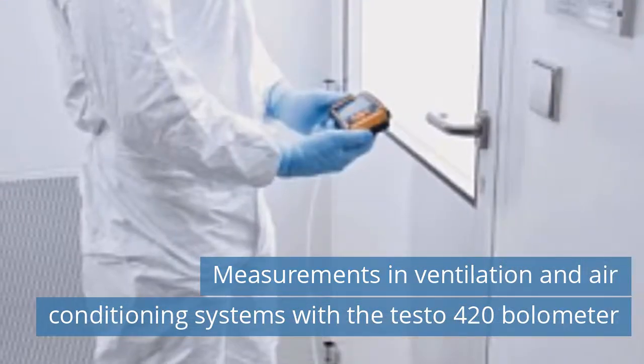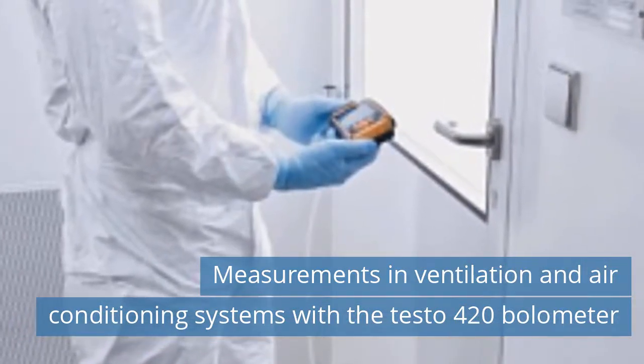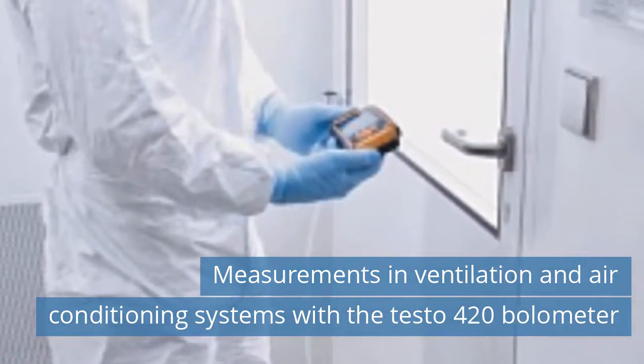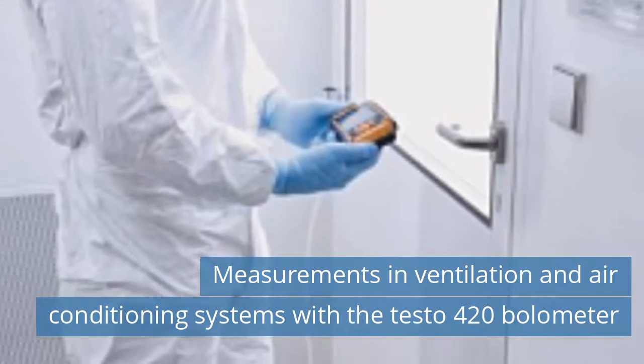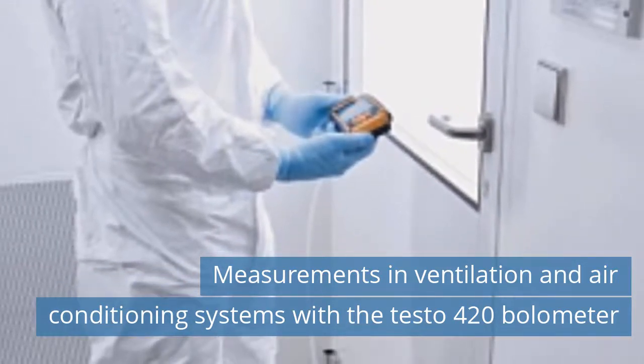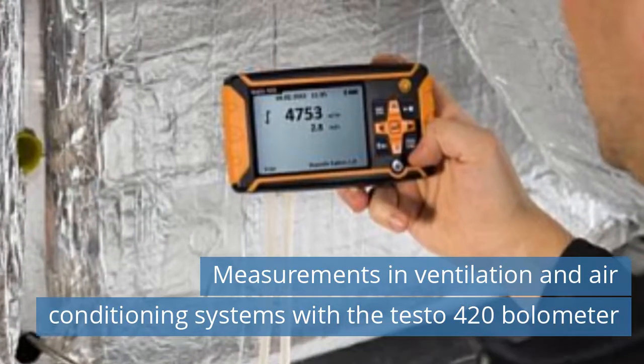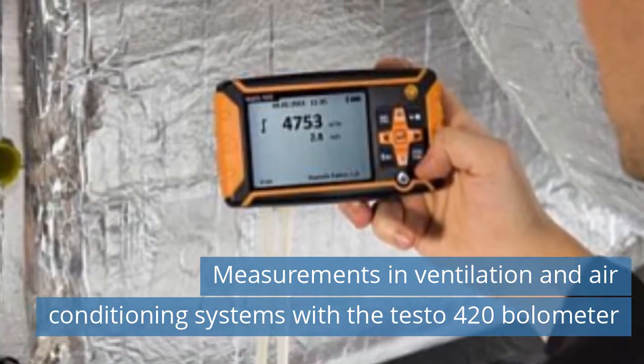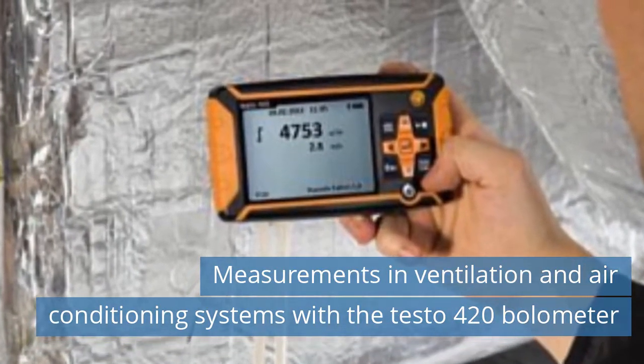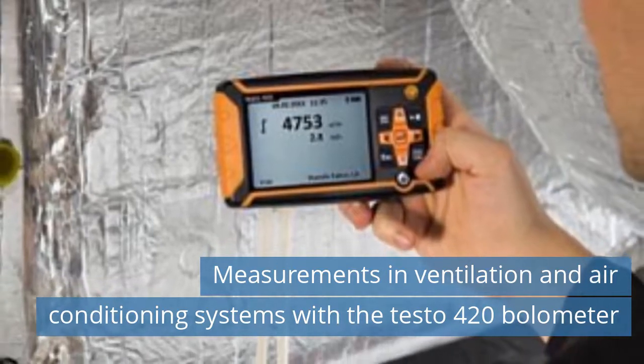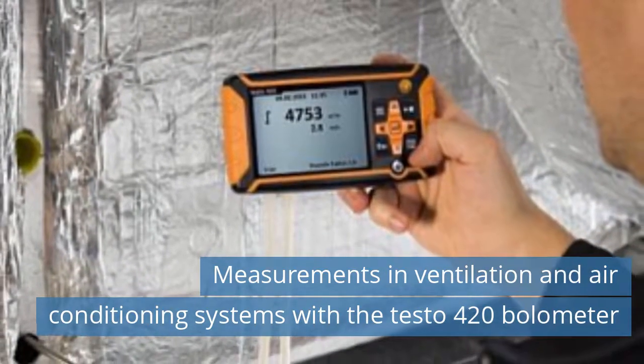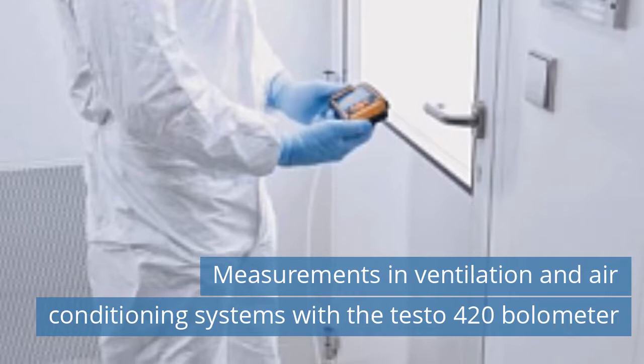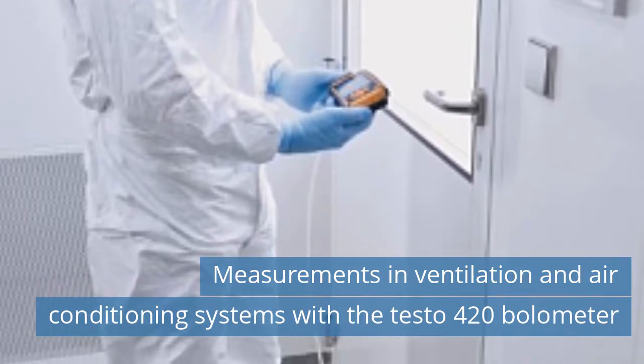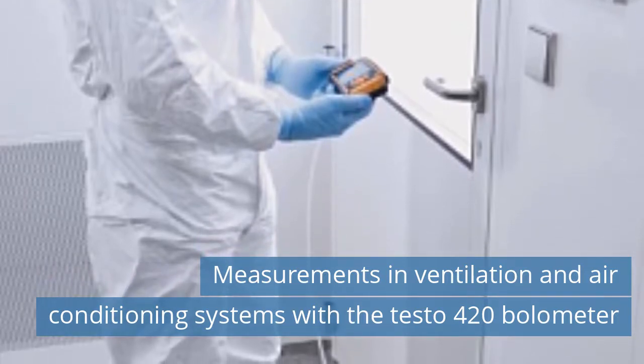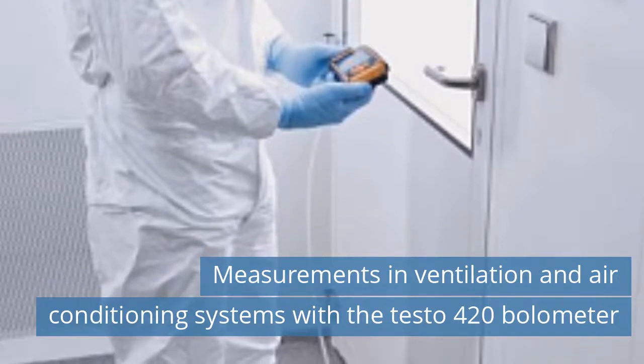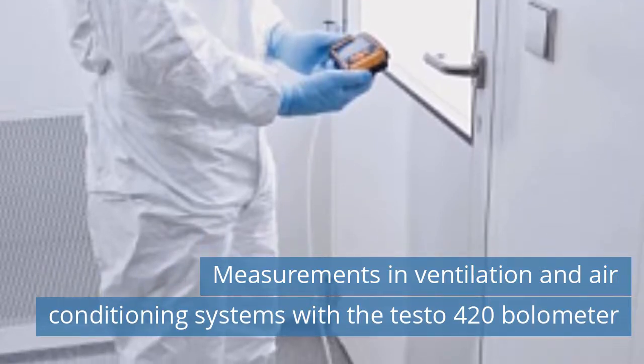Poorly estimated ventilation or air conditioning airflow can lead to overconsumption of energy as well as poor air quality. Testo provides the solution to allow the end customer to benefit from a system that is adjusted, balanced and tested, in order to comply with required regulations. The Testo 420 volume flow hood, or bolometer, allows commissioning or installation engineers to perform balancing and take measurements on large air inlets and outlets, precisely adjusting their volume flow.